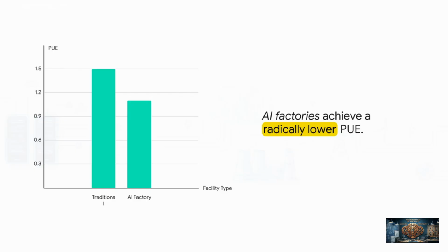This creates an incredible efficiency story around something called PUE, or power usage effectiveness. Traditional data centers using those massive mechanical air chillers hover around a PUE of 1.40 to 1.60. But modern dry-cooled AI factories drop that all the way down to near 1.05.